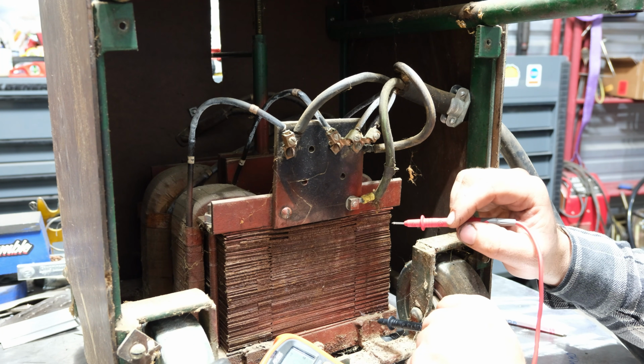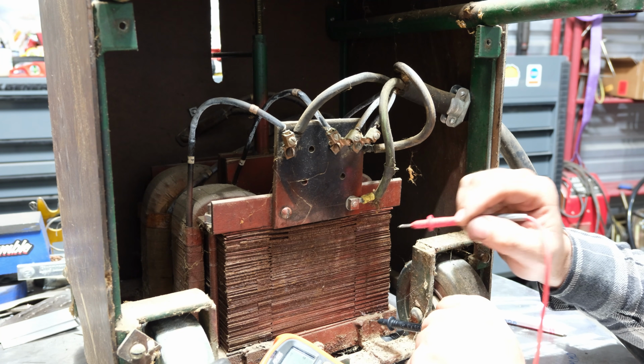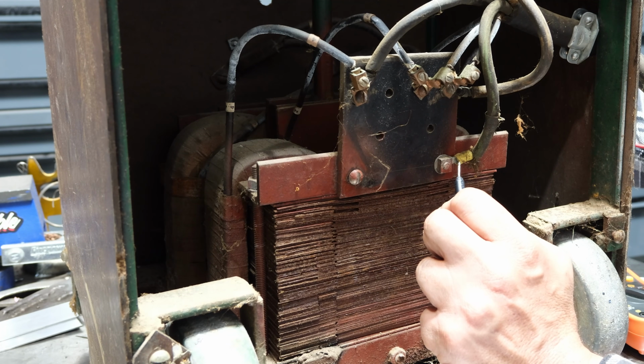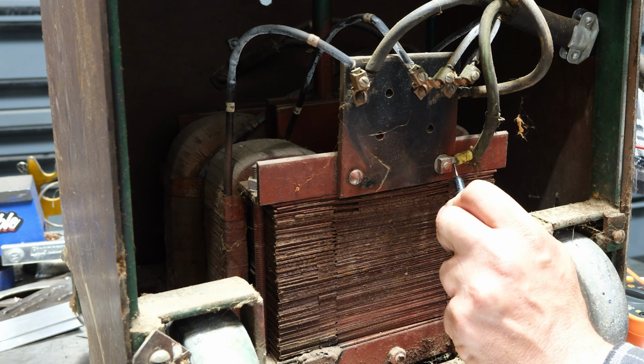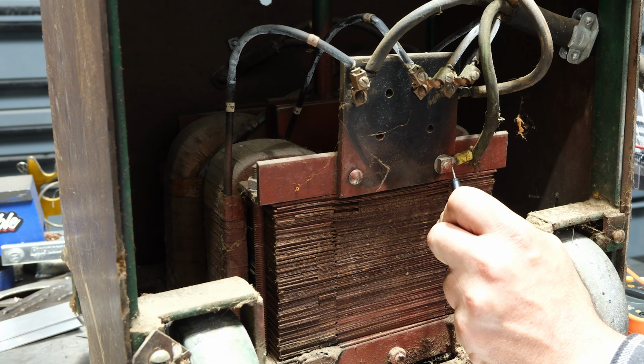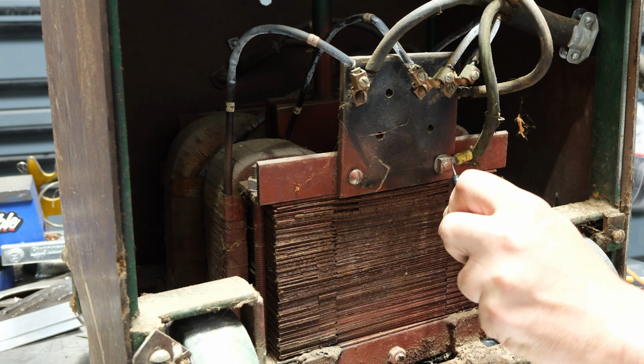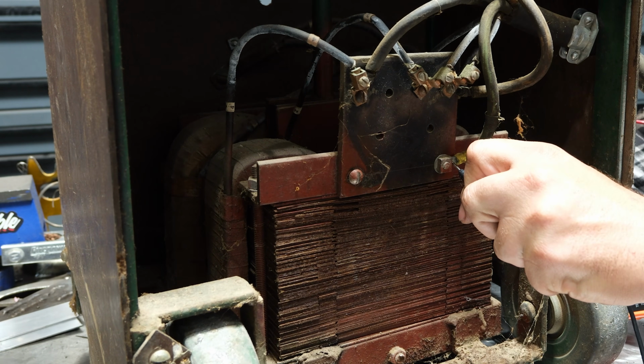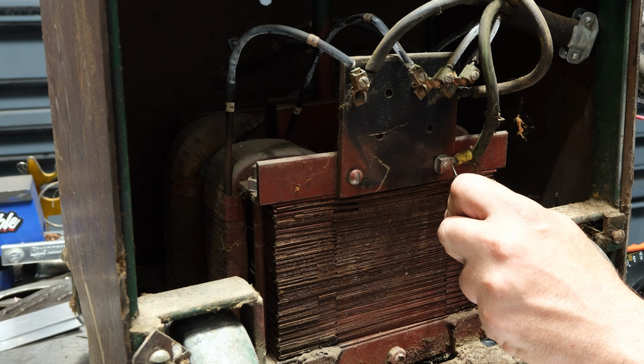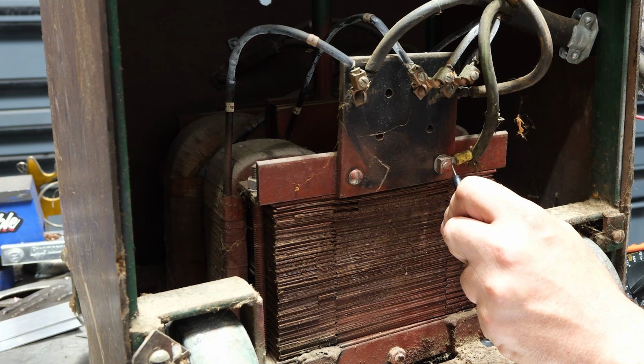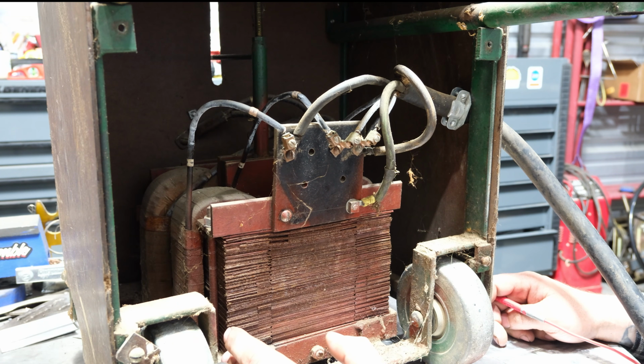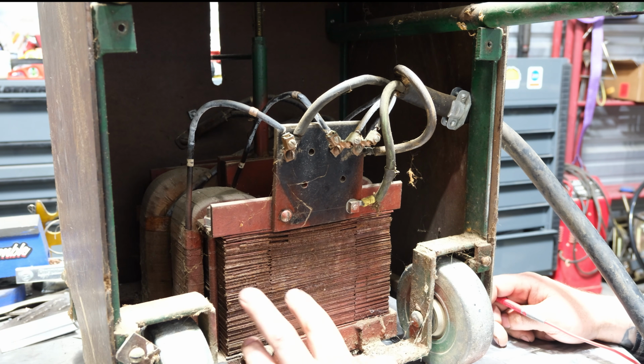Now I'm going to go in the front of the welder and test that the outputs are not shorted to ground either. Okay, I got it hooked up to one terminal on the front. Got no reading, that's great. Hooked on the other terminal and no reading. All of that shows me that this thing's reasonably safe to plug into the wall. Nothing is shorted out to the case, and the transformer itself is not shorted out to the core either, so that is a great sign.